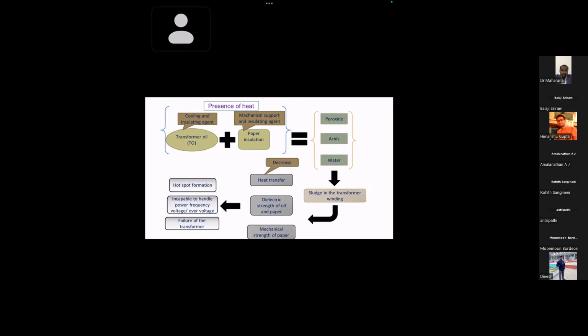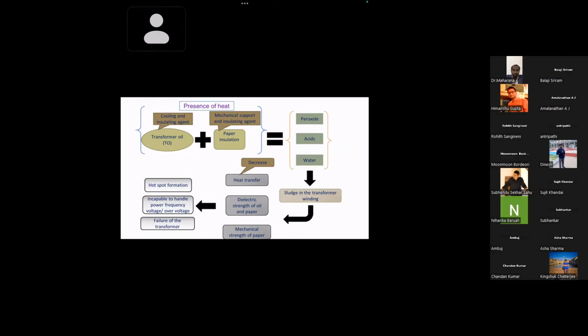Transformer oil's major characteristics are cooling and insulation. When it is combined with paper, there are multiple parameters, like mechanical strength and chemical structure, and when both are combined, it's very difficult to maintain strength and rigidity for a long period of time. Most of the time, due to weakening of the solid insulation such as kraft paper and pressboard, the transformer is taken for maintenance, and they remove the paper and pressboard and replace them with new ones. New pressboard and new paper are supplied.